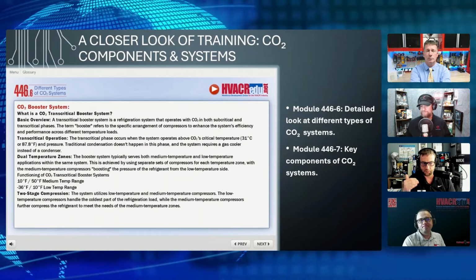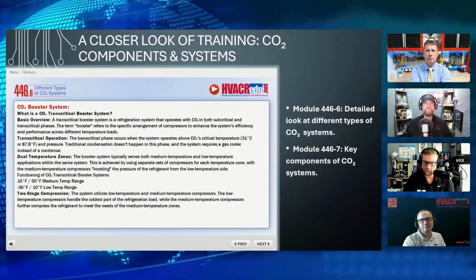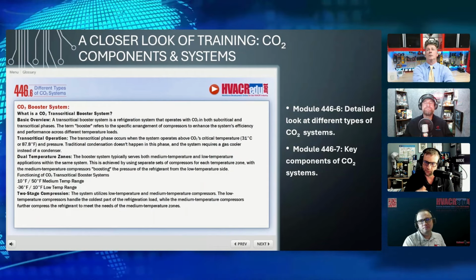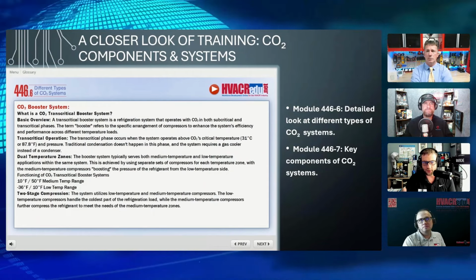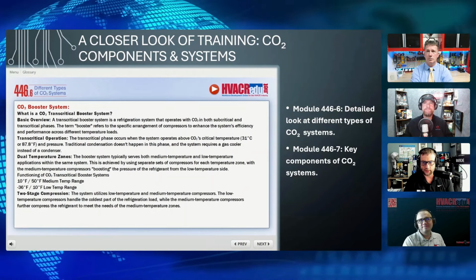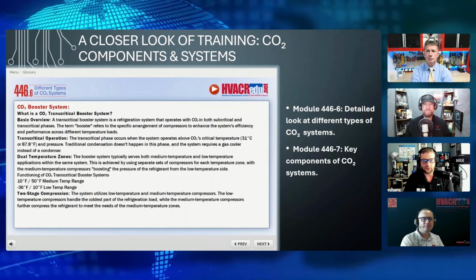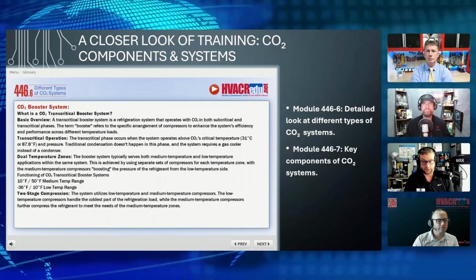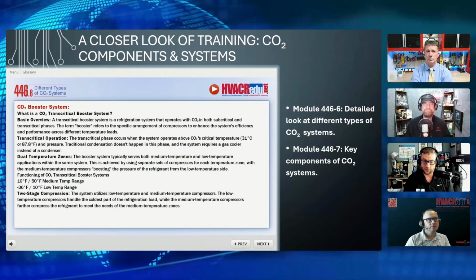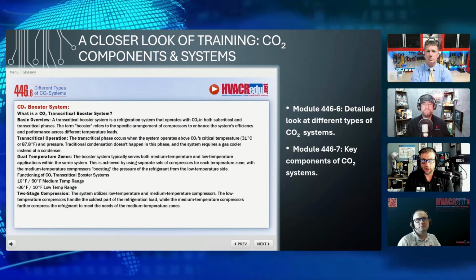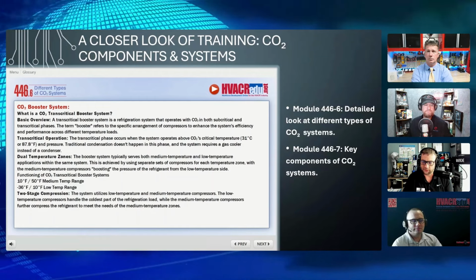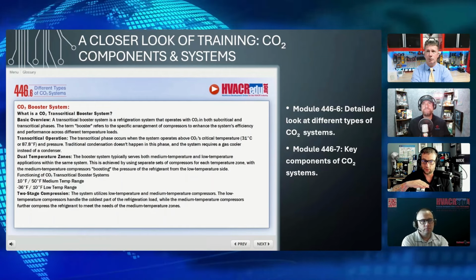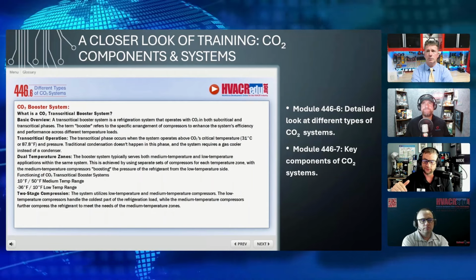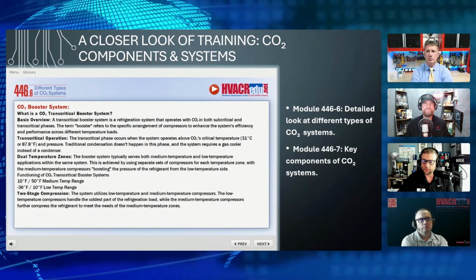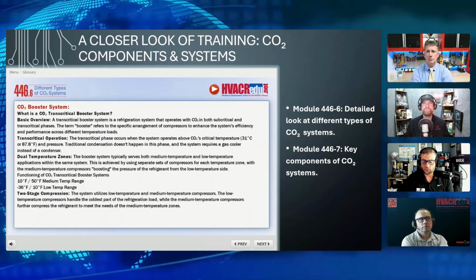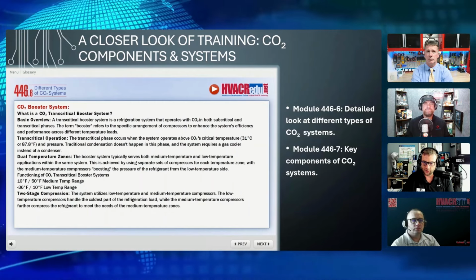Once again, it's 87.8 degrees saturated, which is 1,055 PSI. That's the critical point of CO2. I don't like calling it a transcritical system because it makes it sound very scary, and not every system is transcritical. If it's in Alaska, is it running transcritical? No. You have a TD, the difference between the ambient and your actual saturated condensing temperature. So if your ambient is 100 degrees and you have a 20 degree TD, you're going to be operating at about 120 degrees saturated.